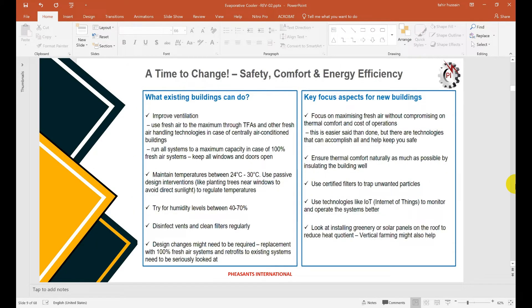There are two types of buildings: existing buildings and new buildings. For existing buildings, because of COVID, ASHRAE recommends maintaining temperature 24 to 30 degrees centigrade to allow more fresh air. We should use fresh air to the maximum through treated fresh air and other fresh air handling technology. In central air conditioning buildings, run the system at mostly 100% fresh air, maintain temperature between 24 to 30 degrees centigrade, and target humidity level between 40 to 70 percent. For new buildings, we must focus on increasing fresh air to bring more oxygen and improve comfort.